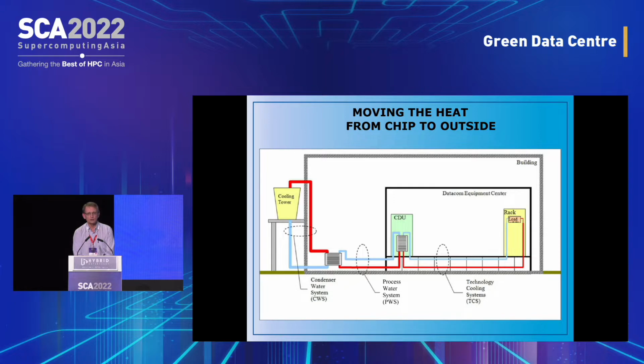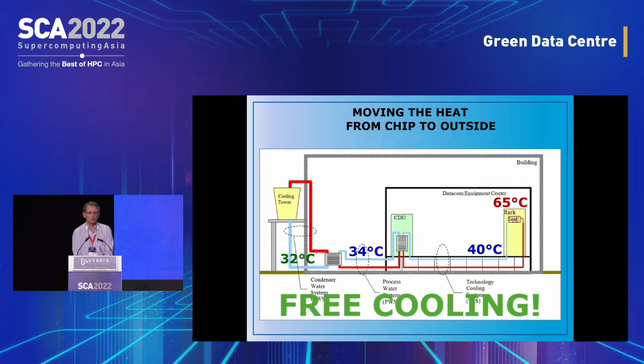So just look at the process: we're basically passing a fluid through the IT equipment, picking up the heat, and transferring it through a couple of steps to outside, and we don't need a chiller or a compressor. All we need to do is move that fluid around. So if we want 40 degrees on the internal part, we could be doing 34 at the secondary loop, and we can get 32 degrees from a cooling tower all year round in Singapore - we call that free cooling. So if we're doing liquid cooling, this is the kind of thing we ought to be looking at.